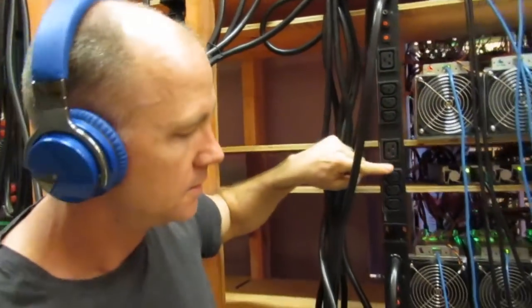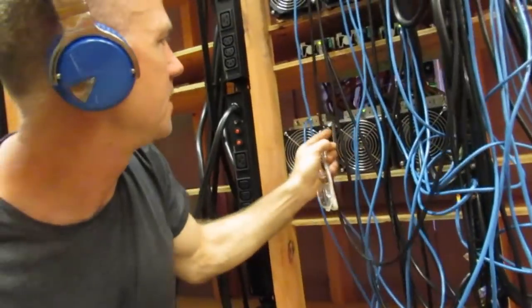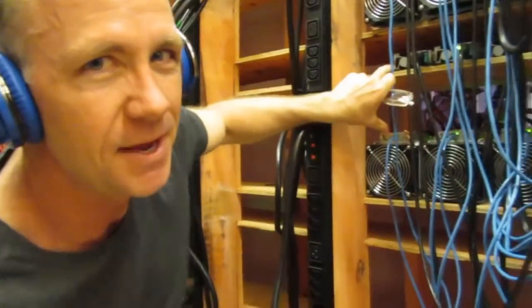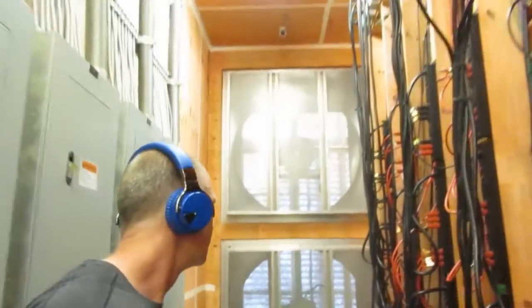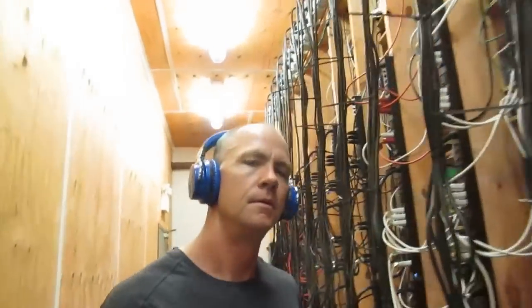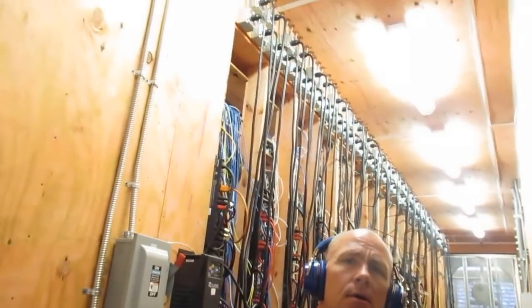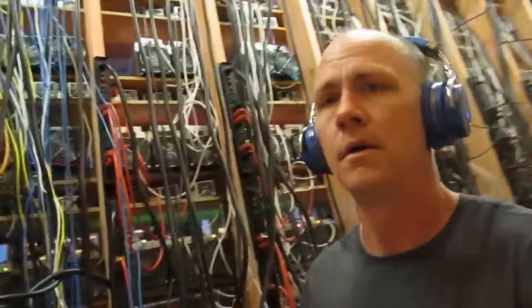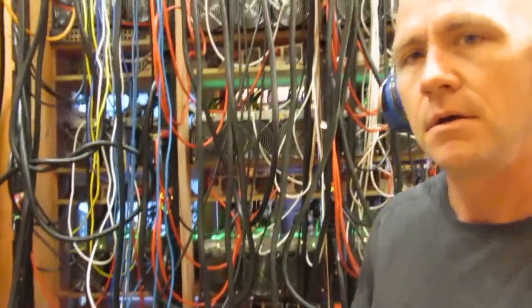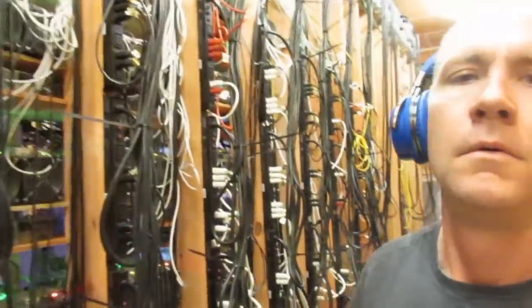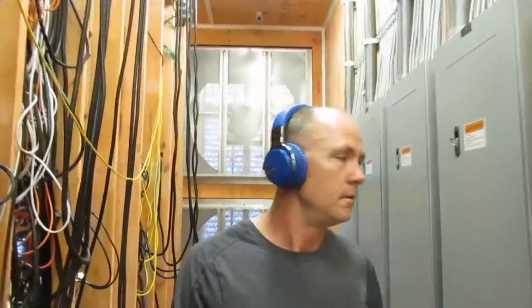We found some good basic PDUs that have 8 connections and 2 breakers. And each of these miners we have a shelf for power supplies, and we have a shelf for the miners. Newer miners don't necessarily need those, and we could probably put them a little closer together, but we did a pretty good design here, and we're not getting reverse airflow. So you can see each side has 5 panels, and each side has I believe it's 90 of the 30 amp receptacles. We can add more if we need to. We have additional space on the panels. But since this is sized for a combination of electricity, heat, and cooling, I expect once we fill this up that we're going to then do other build outs in order to be able to add more miners.